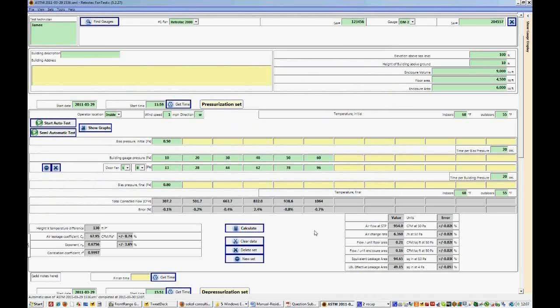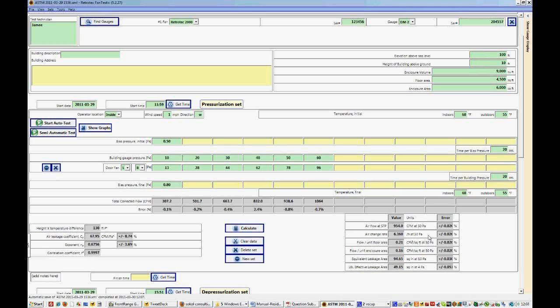So that equation, the equation of the line that we just saw, is used to calculate all the results that we see here. And these are the results that you would share with your customers. So we have air flow at STP in CFM at 50 pascals, an air change rate, so air changes per hour at 50 pascals, a flow per unit area, unit floor area, in CFM per square foot at 50, a flow per unit enclosure area in CFM per square foot at 50 as well.